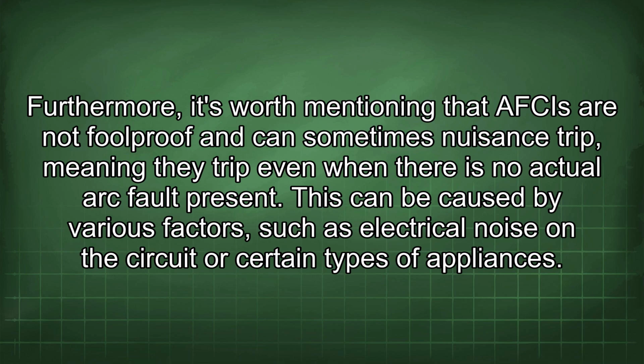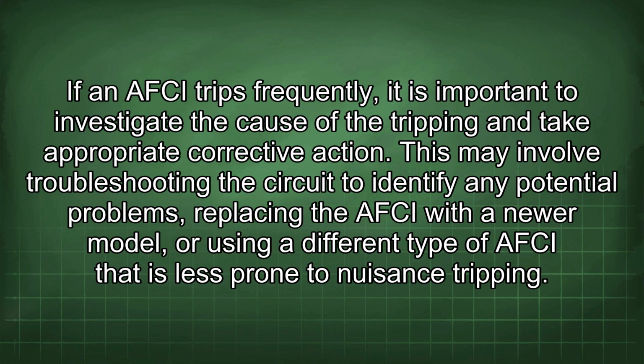Furthermore, it's worth mentioning that AFCIs are not foolproof and can sometimes nuisance trip, meaning they trip even when there is no actual arc fault present. This can be caused by various factors, such as electrical noise on the circuit or certain types of appliances. If an AFCI trips frequently, it is important to investigate the cause of the tripping and take appropriate corrective action.